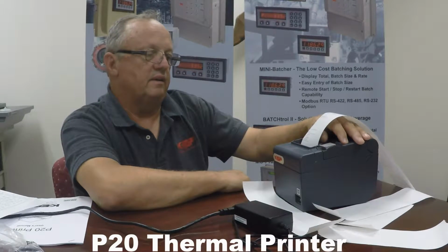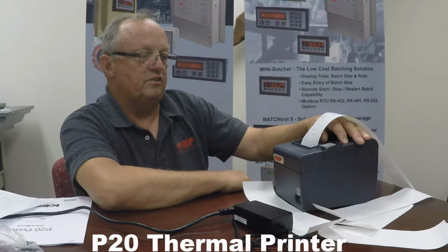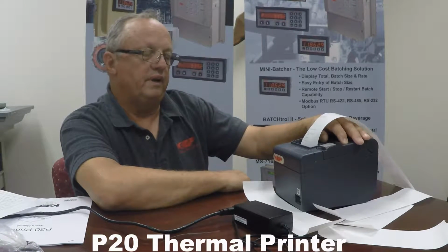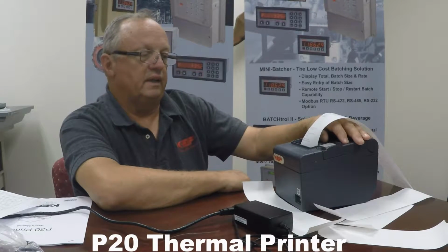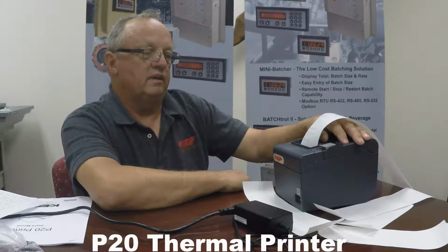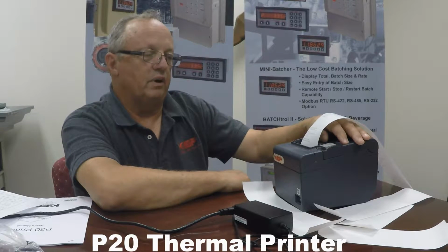This is the location where it's going to have data receive error. This is going to be 5 quick depressions followed by a long depression. 1, 2, 3, 4, 5. In this case, it's telling me that it can either ignore bad characters or print a question mark. I'm going to leave it where it's going to print a question mark if it doesn't identify the character.